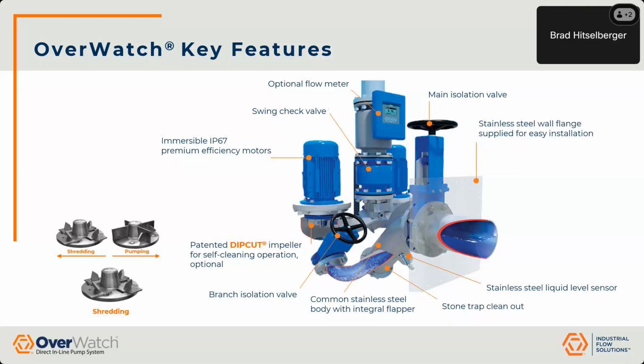The purpose of that is to protect the integrity of the pump. So if you have something that comes down the collection network that should not be there, we know that things get down the collection network that people aren't supposed to flush, but it happens in real life. The purpose of that is for it to not come up and damage the pump where the volute is. If it's a heavy piece of debris, the best example I hear out in the field and what I usually see is a 2x4 or a chunk of concrete, something heavy that's going to be an odd shape. It will sit down in that stone trap cleanout, and it's an inspection port for you to go and remove that debris if it's a heavy object.